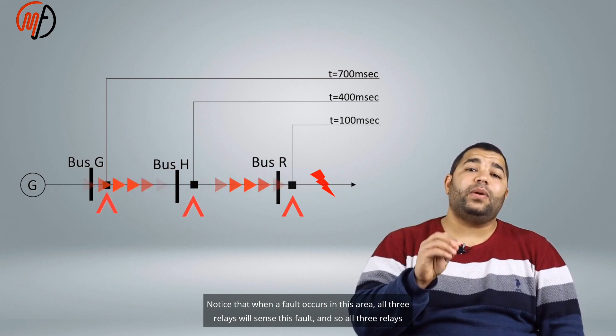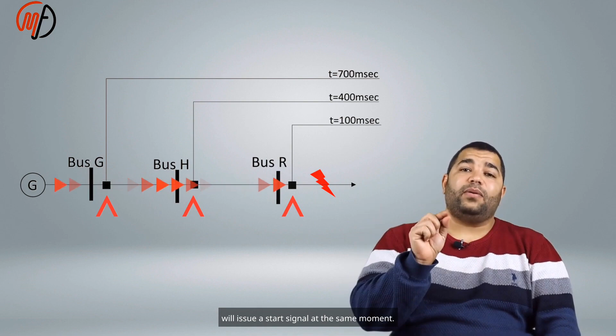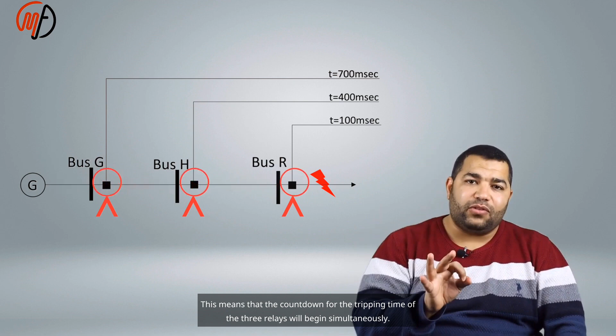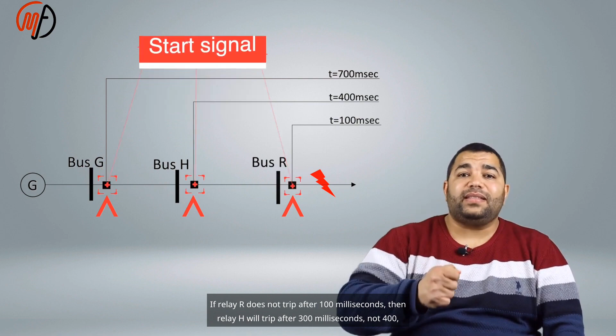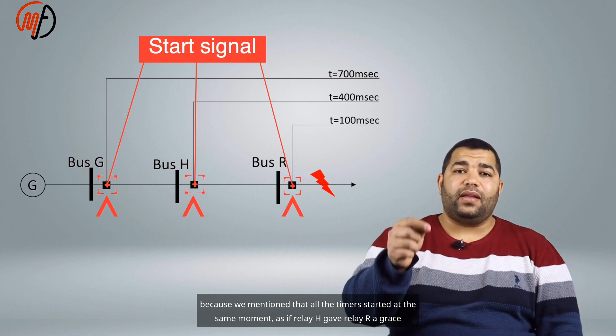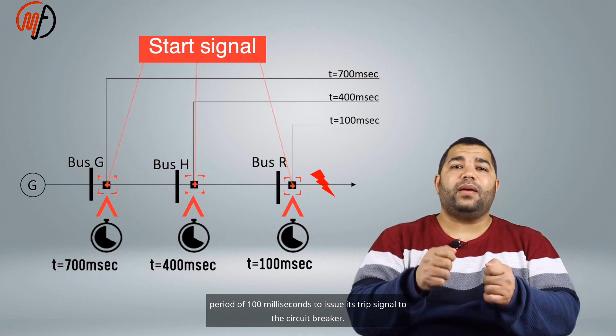This process happens gradually. Notice that when a fault occurs in this area, all three relays will sense this fault, and so all three relays will issue a start signal at the same moment. This means that the countdown for the tripping time of the three relays will begin simultaneously. If relay R does not trip after 100 milliseconds, then relay H will trip after 300 milliseconds, not 400, because all the timers started at the same moment, as if relay H gave relay R a grace period of 100 milliseconds to issue its trip signal to the circuit breaker.